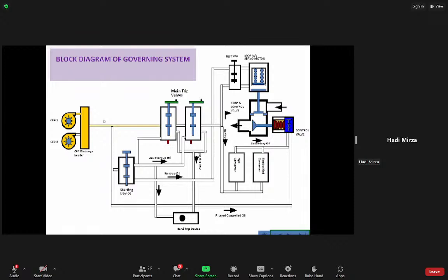When we start the control fluid pump, pressure builds up in the discharge header, and then it directly goes to trip oil pressure and then to filtered control valves. Then the starting device. First it will go to three parts: one main trip valve, starting device, and then control valves. This is a filtered oil. There is a filter in between this control valve and the discharge header.